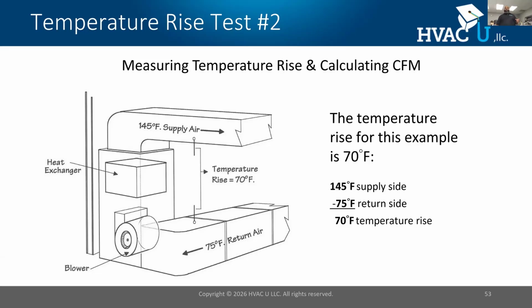Manufacturers produce temperature rise ranges for their equipment. So if my furnace says 35 to 65 temperature rise and I measure a 70, guess what? My bonnet is overheating. It's going to short cycle on high temperature limit. I don't have enough airflow circulating through the system. This is a great way to evaluate really quickly if you have an airflow problem. And you can also use this in formulas to calculate system airflow.